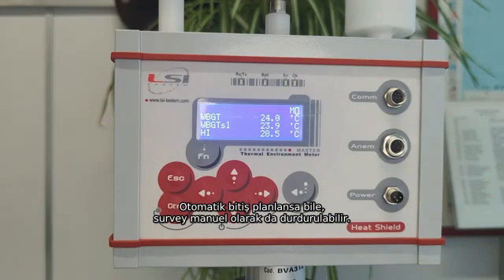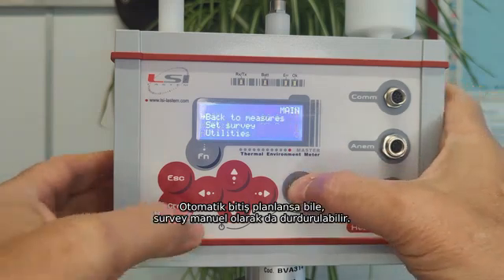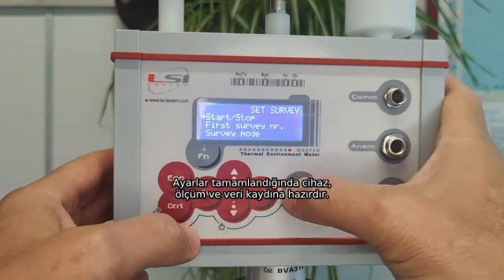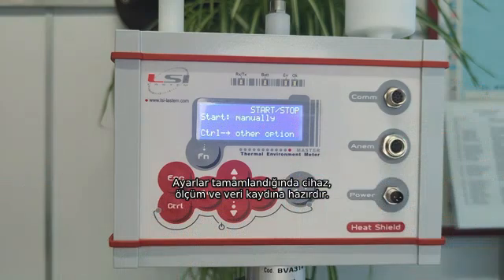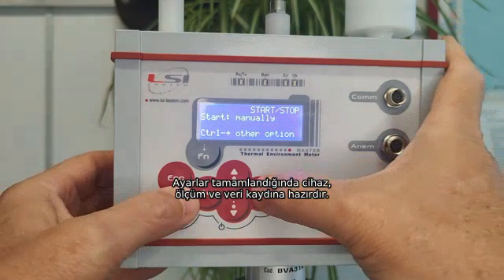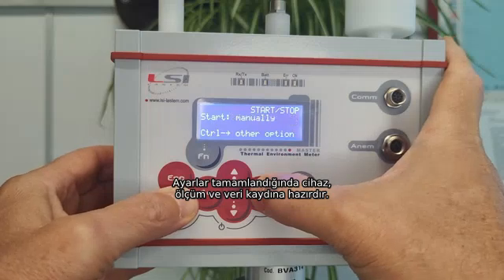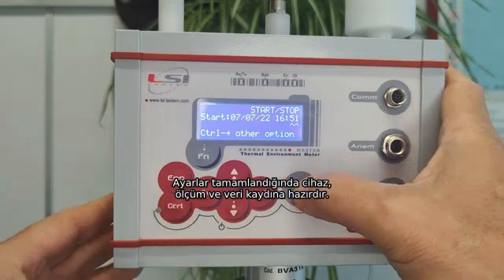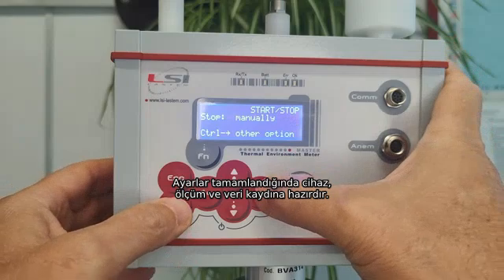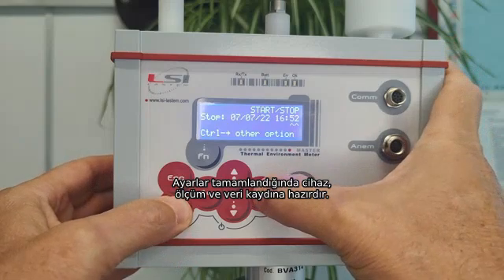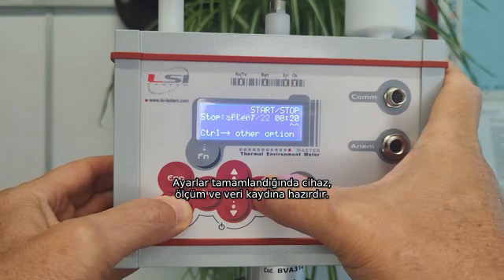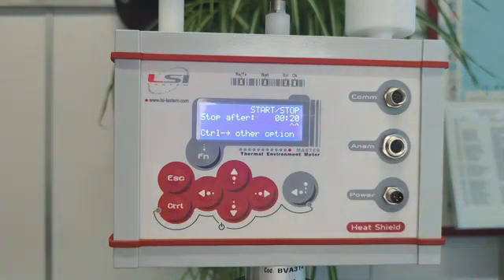Optionally, from the Set Survey menu, it is possible to set the HeatShield device to start data storing manually or automatically at a certain date and time. Even the stop of the survey can be programmed to be manual, a certain date and time, or after a certain time since the survey has started.